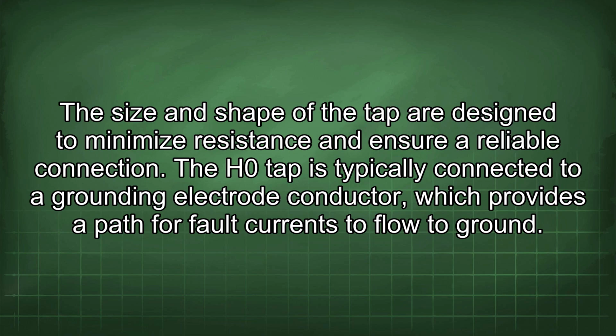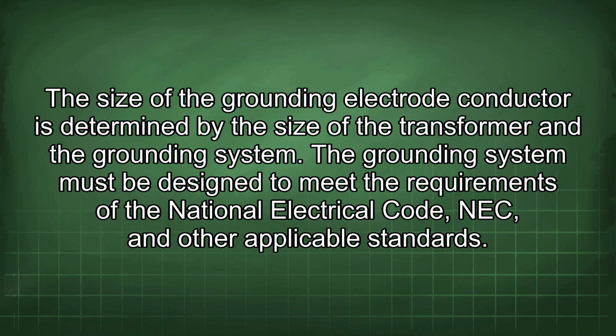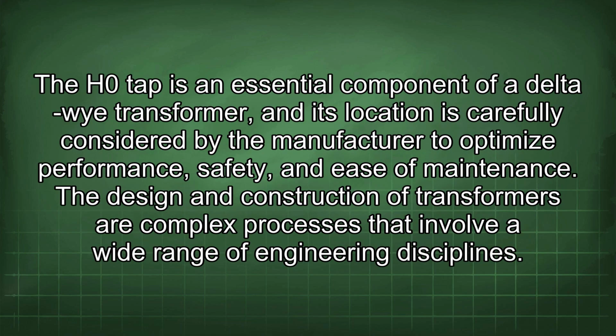The H0 tap is typically connected to a grounding electrode conductor, which provides a path for fault currents to flow to ground. The size of the grounding electrode conductor is determined by the size of the transformer and the grounding system. The grounding system must be designed to meet the requirements of the National Electrical Code, NEC, and other applicable standards. The H0 tap is an essential component of a delta-wye transformer, and its location is carefully considered by the manufacturer to optimize performance, safety, and ease of maintenance.